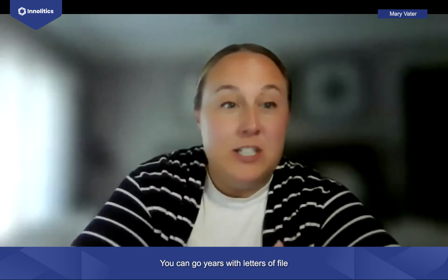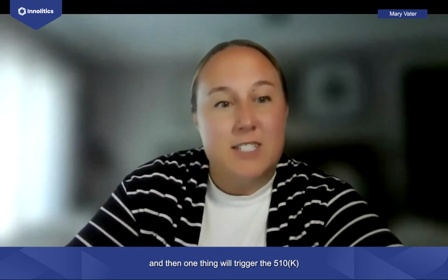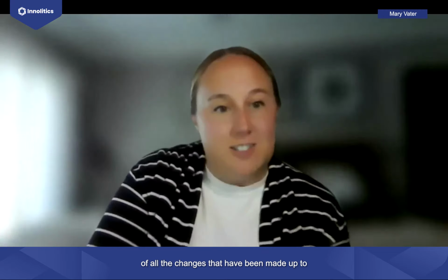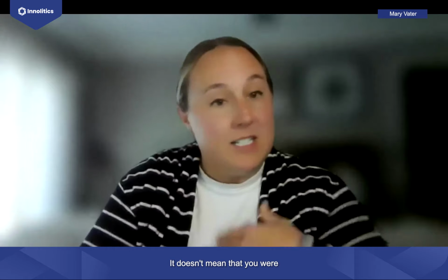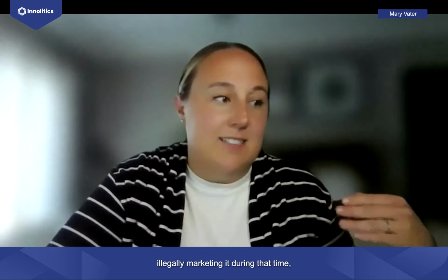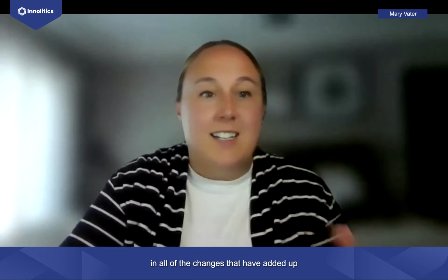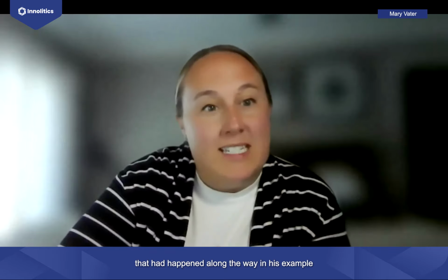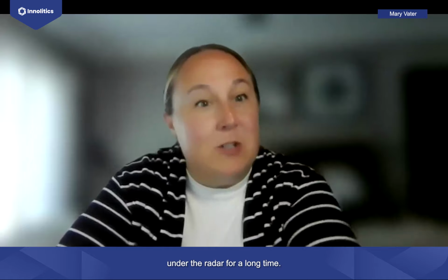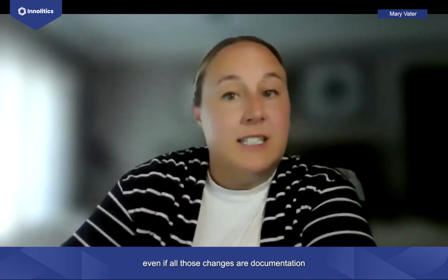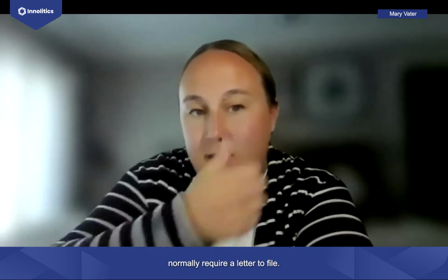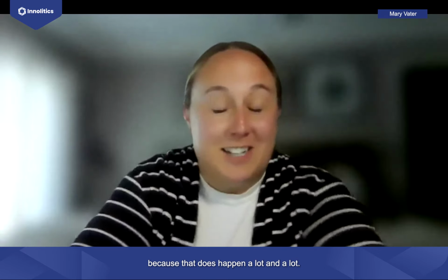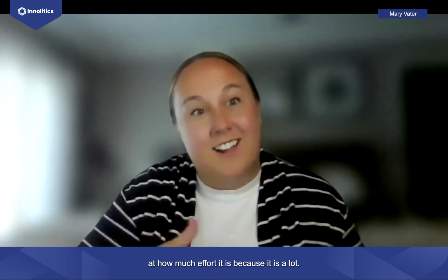Yeah, all the time, actually. You can go years with letters to file, and then one thing will trigger the 510(k), but your documentation needs to be reflective of all the changes that have been made up to that point in time. It doesn't mean that you were illegally marketing it during that time, but the FDA is interested in all of the changes that have added up to where the device is now that they're reviewing. Like George mentioned, there may have been some other changes along the way in his example that probably should have triggered a new 510(k) that managed to slip under the radar for a long time. But even if all those changes are documentation only, which wouldn't normally require a letter to file, everything has to be described in detail in the new submission. That's a good question, because that does happen a lot. And a lot of times clients are surprised at how much effort it is, because it is a lot sometimes.